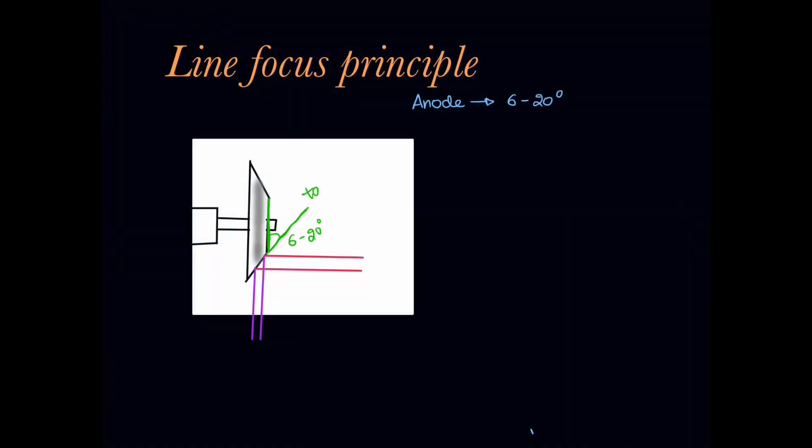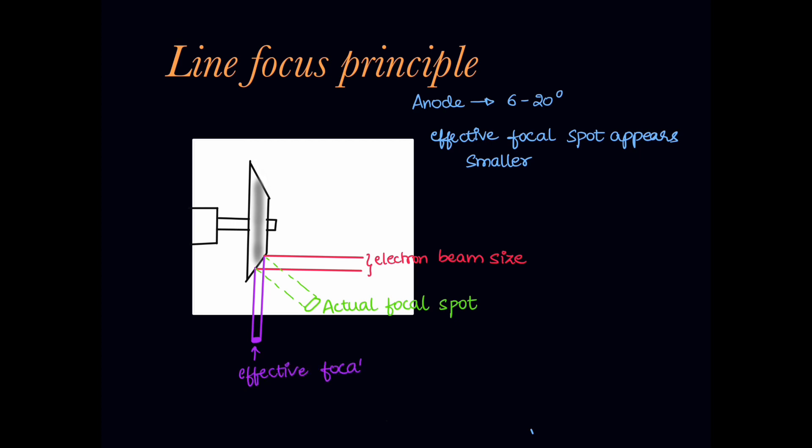Anode, usually the rotating anode is kept at an angle of 6 to 20 degrees which is also called as a target angle in order to focus the primary beam towards the patient. The electron hits the target at the focal spot but this focal spot, when visualized from down, from the angle of patient the effective spot will be smaller than the actual focal spot and this principle is called line focus principle.